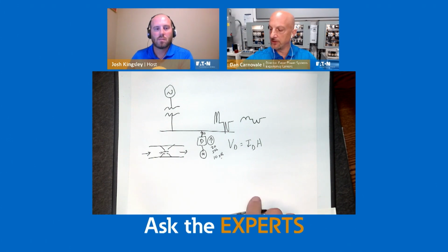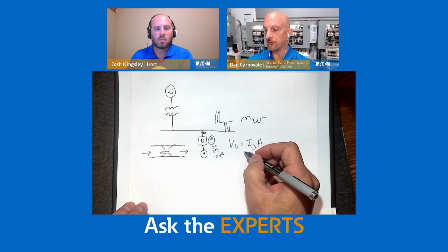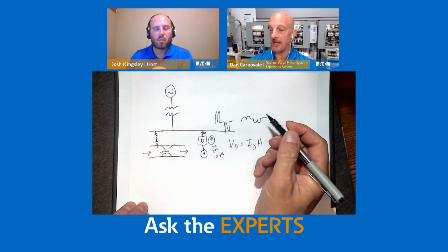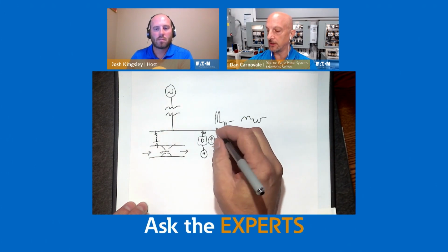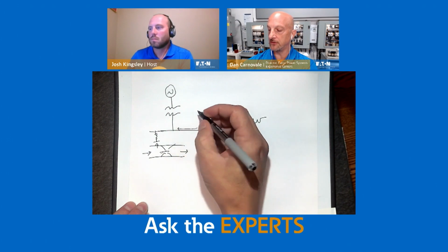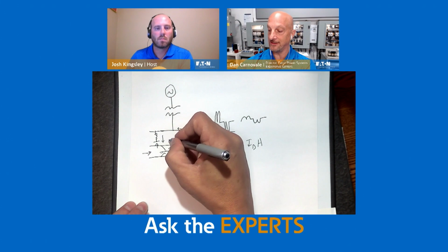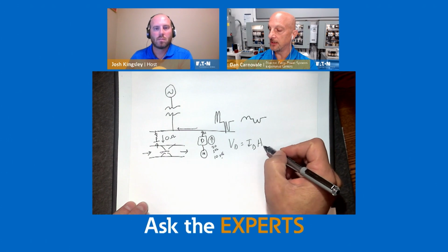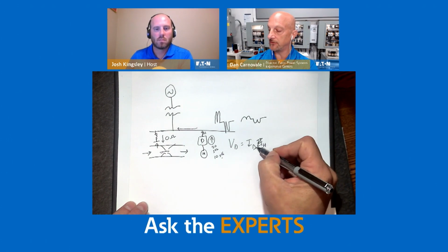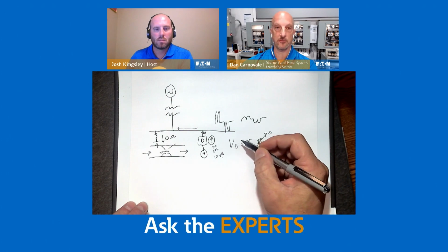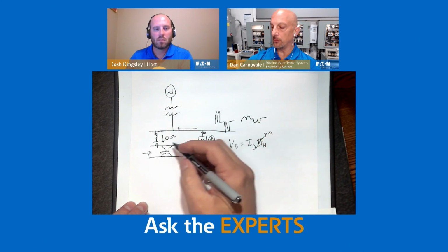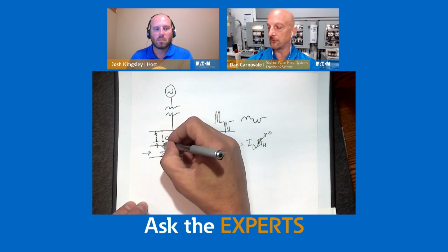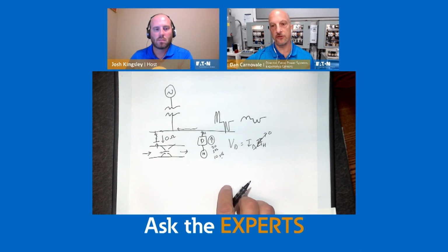As you look at other things, if we try to take the current and make it go somewhere else, we could put a filter over here. A filter looks like a reactor and a capacitor in series. At a particular frequency, let's say this fifth harmonic current, when the current gets to this point, it wants to divide and go according to impedance. If this was ideally 0 ohms, then even if it's 100 amps times harmonic impedance, our voltage distortion goes back to zero. In reality, it's not going to be zero, but this is how harmonic currents flow through the system. Most times when you make a filter like this, half of the current or so goes this way, half goes this way. So those are two things you could do.